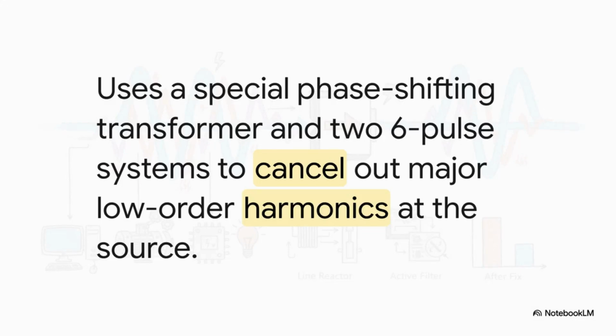Okay, next up is a much more clever design, the 12-pulse rectifier. This thing uses a special transformer to feed two separate rectifiers that are deliberately set out of sync with each other. And the result is pretty slick. The worst harmonics made by one rectifier get canceled out by the other one. It's a really smart way to tackle the problem right at the source.